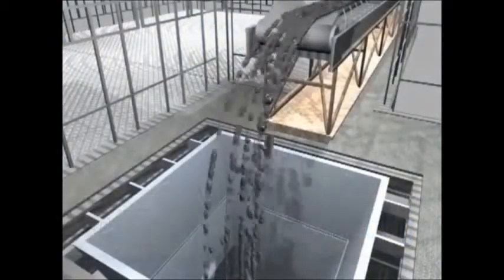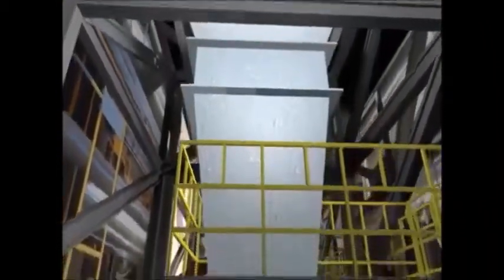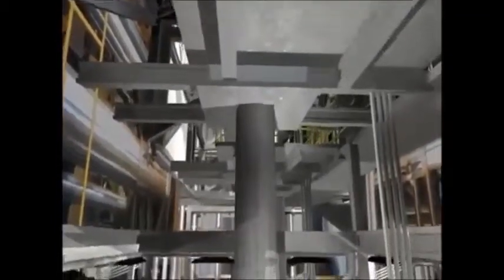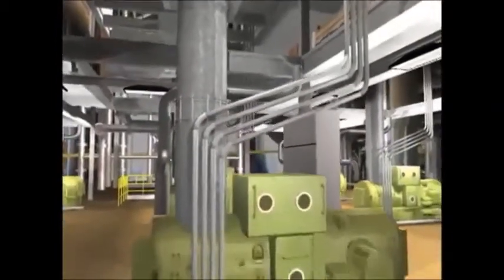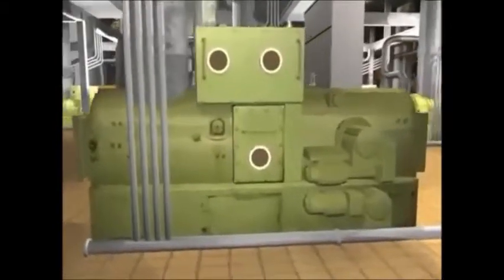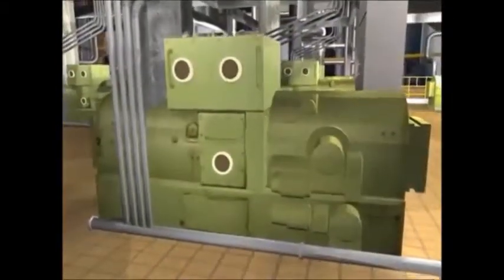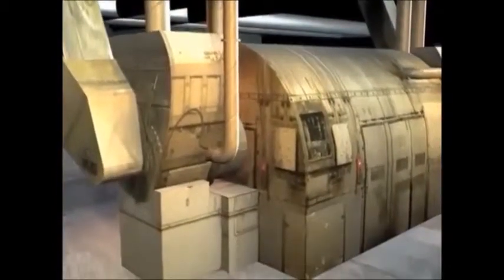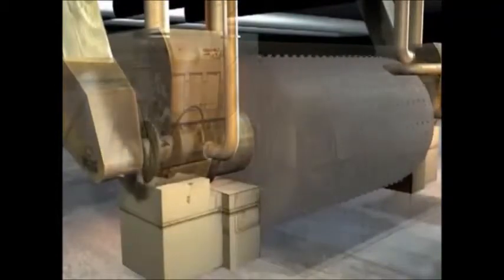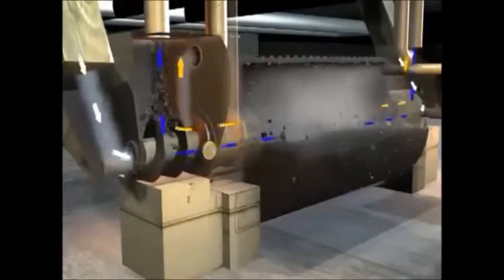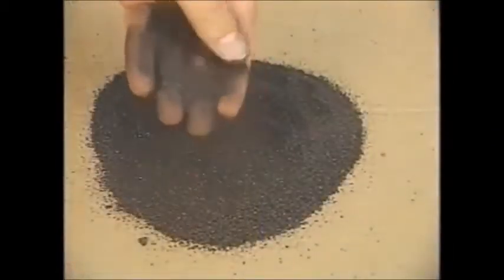Once inside the plant, up to a 30-hour supply of coal can be stored in bunkers. Coal moves from the bunkers to feeders to be measured and moved to pulverizers. Each generating unit has 16 coal feeders that supply 8 pulverizers. Coal enters the pulverizer and spins in a large drum, where hundreds of steel balls grind it into a fine powder. Now a fine powder, the coal leaves the pulverizers and heads to the boiler. About 335 tons of coal can be pulverized per hour.